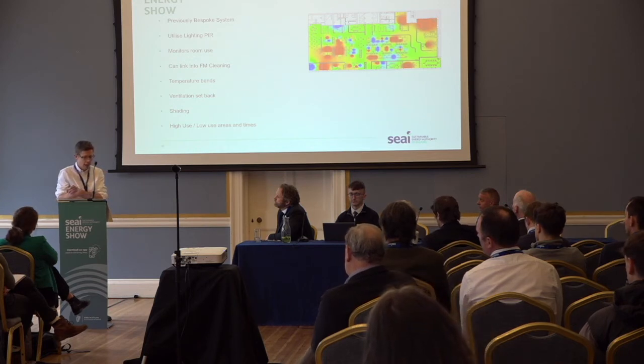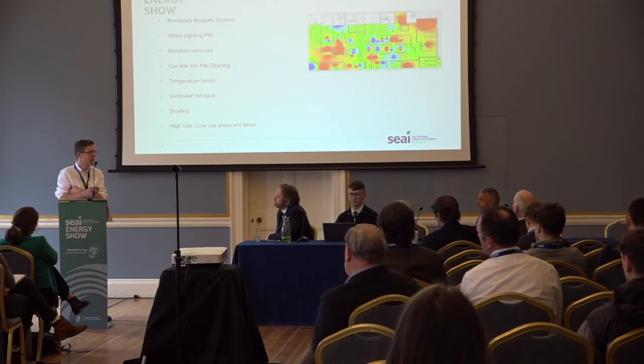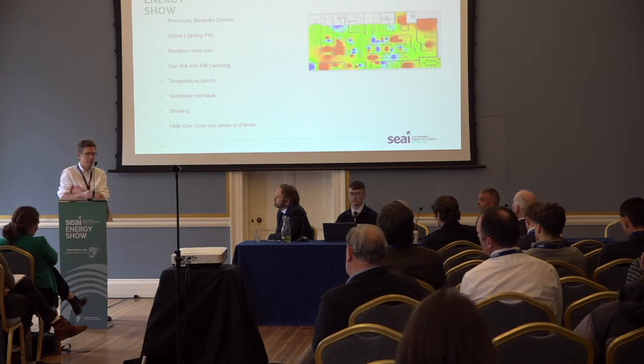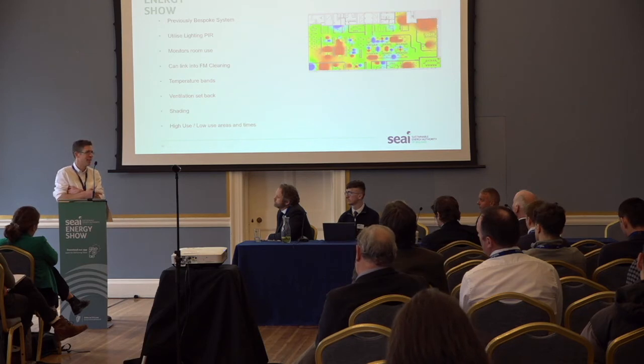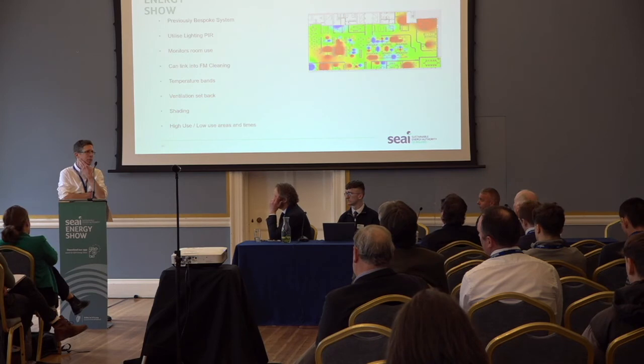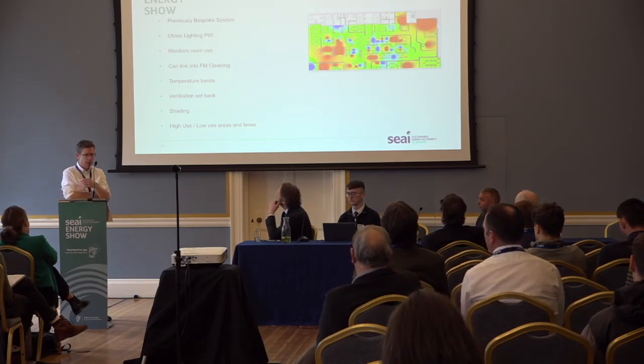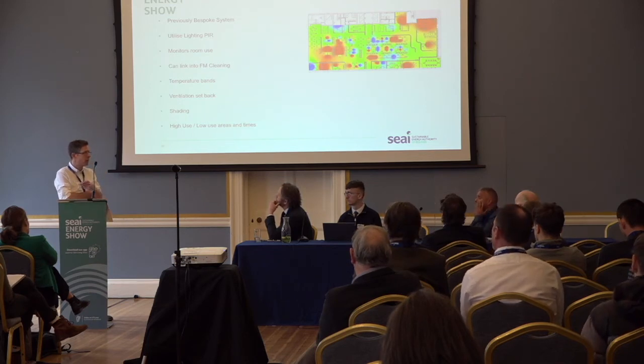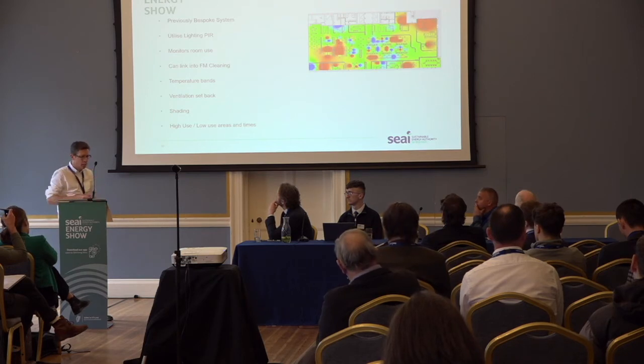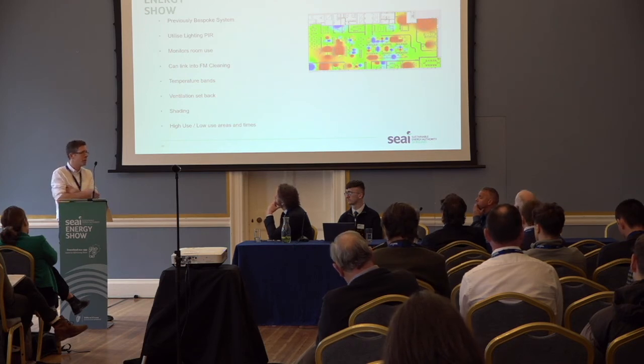The FM teams are using this information from the room booking and other systems to see if rooms are actually occupied - do they need to clean the rooms, do they need staff there, do they need to bring five people in from somewhere else to work in the building? Maybe not, because the rooms might be booked on the system but actually empty. So in terms of integration, it monitors room use, lets us use ventilation setback, and control our high and low level alarms, temperatures and times of operation of the building.